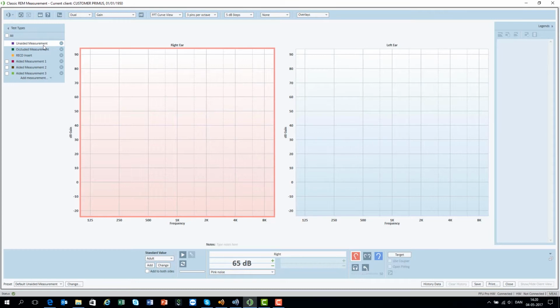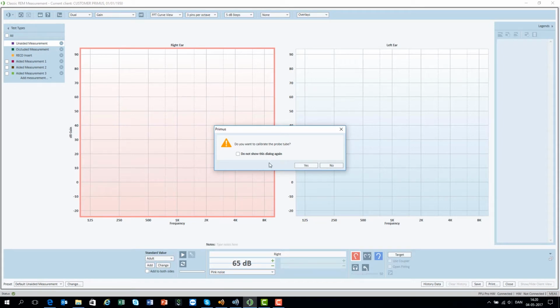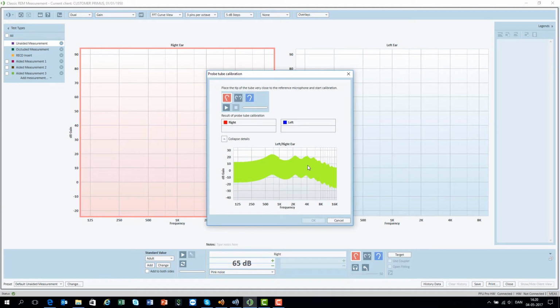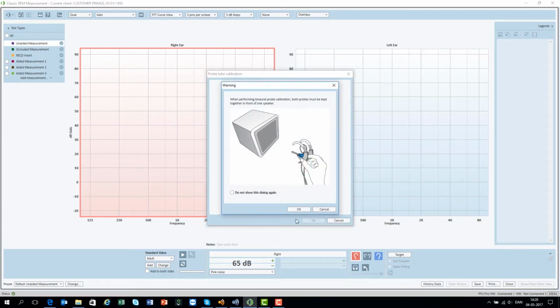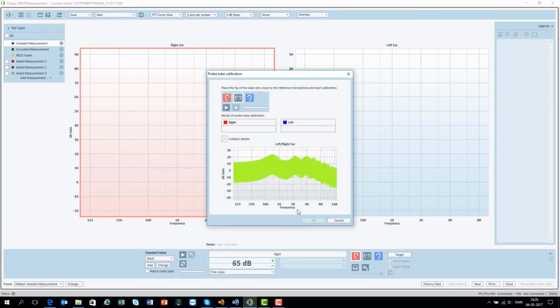To start the probe tube calibration, click on the calibration icon, or when selecting a test type the first time in a session, the system will recommend a calibration. To be time efficient, choose to calibrate both ears and click play. The response of the microphone should ideally be in the center of the green area. The system automatically runs a quality check of the calibration and will start a second calibration if needed.